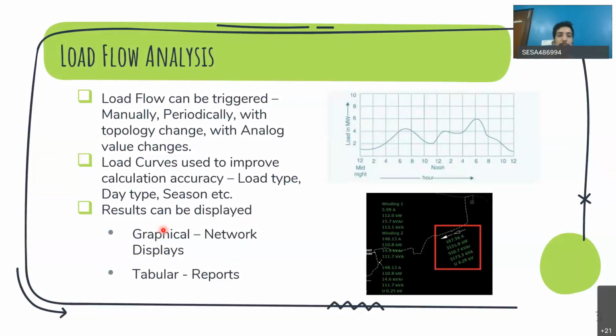Load flow can be triggered manually, whenever the operator wants to run it on a particular feeder, substation, or the whole city, or it can be configured to run periodically—every 10 or 15 minutes, for example—or whenever there's a topology change. Obviously when a breaker trips or a device is opened or closed, the network scenario changes, so load flow must run again to recalibrate the scenario in the control center, and this can happen automatically.